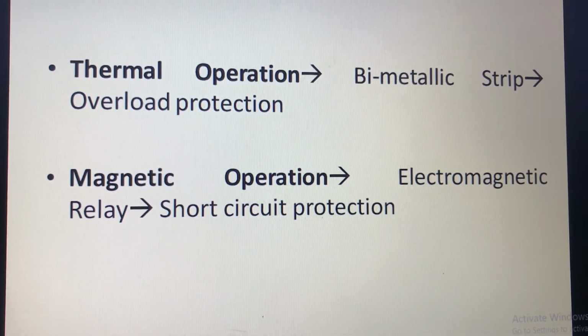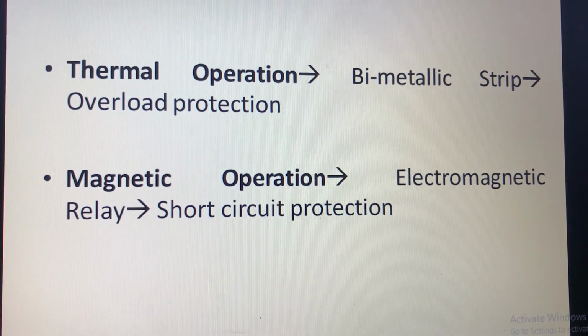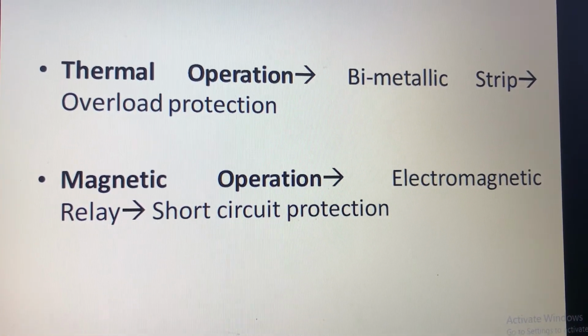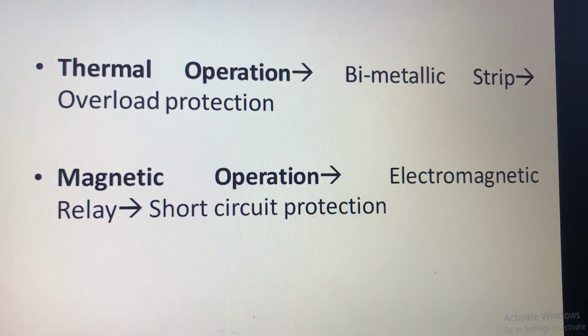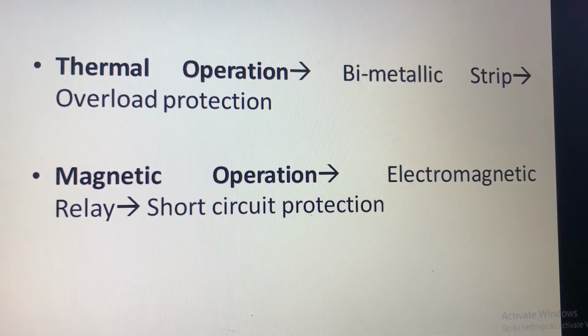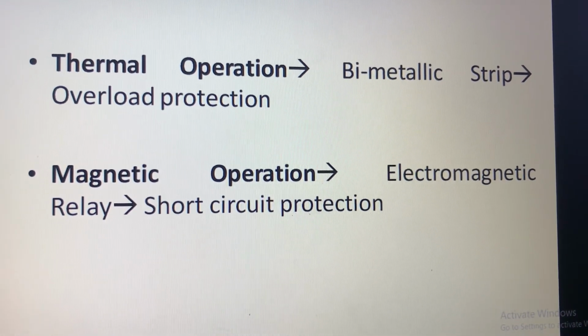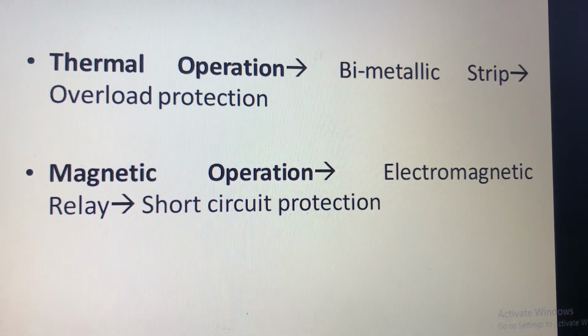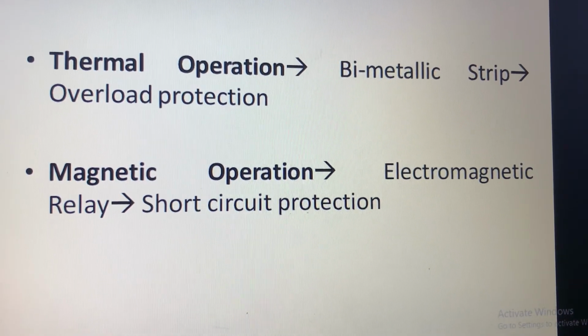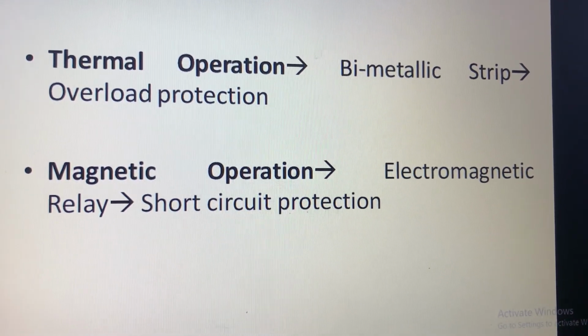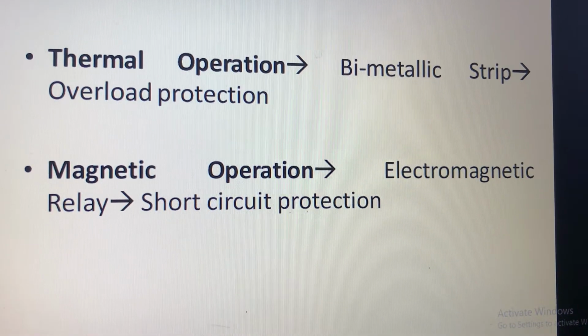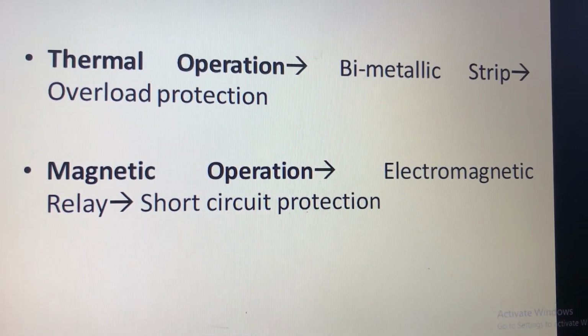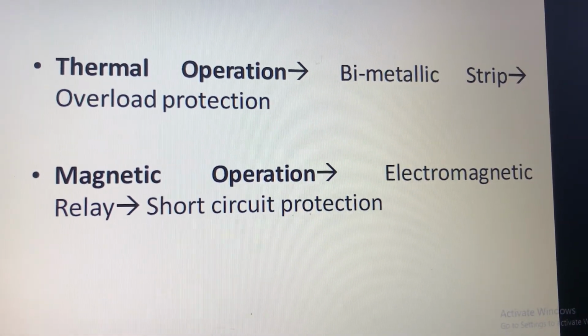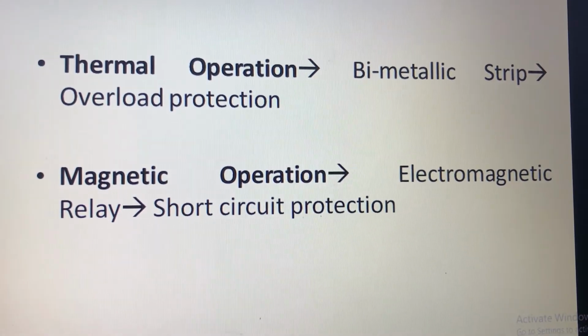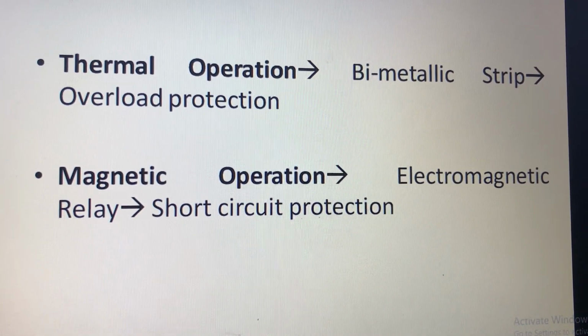Due to this, when the overloading occurs on the system, the one metal bends and it will open its contacts. So this is due to the thermal effect of the current. There is a thermal effect in the current, that is when it flows through the wire or through any conductor, it heats up. It heats up that material. So this effect of the current is used for providing overloading protection in MCB through bimetallic strip.